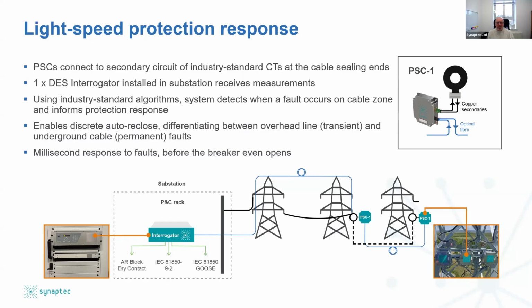So right at the cable sealing end, as the line comes down and the cable comes up, it's probably about 10 meters in the air, we're grabbing those 3 phases, measuring them, and then looping the fiber back into the fiber array so it continues to the far end. But it means all of the sensors are always visible to the interrogator at the center. And then the interrogator has a simple choice. Depending on whether you're ready to adopt 61850 and process bus and station bus or not, we can either inform the protection scheme using dry contact, or we can use basic 61850-9-2 sample values or 61850 GOOSE.